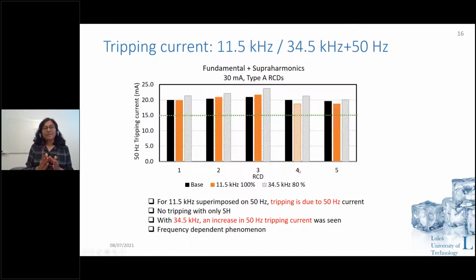So then next, we had 11.5 kilohertz, and we compared the same with 34.5 kilohertz also. So now we have a case where we have 100% of 11.5 kilohertz and 80% of 34.5 kilohertz. And you can see for the 50 hertz tripping current, in the case of 34.5 kilohertz, for all type A RCDs, a higher tripping current is required for the fundamental. So from this we concluded that the tripping is first due to the 50 hertz component, because the 50 hertz component in all the three cases, although different, is not that different. So mainly the tripping in these RCDs is caused by the 50 hertz component.